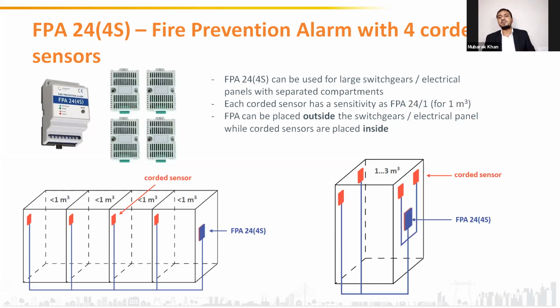Or this FPA 24 4S can be used to monitor multiple cabinets. So normally if we have more than one cabinet in an electrical switchgear, you can install the sensors in each cabinet, and FPA can be mounted at one common location. Okay, any combination you can use. Normally for the Indian scenario, for my customers, I prefer to propose FPA 24 4S only because it becomes economically much cheaper for the customer.